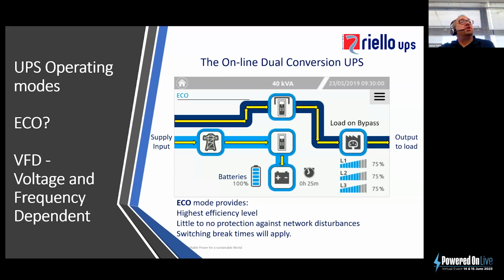Now, one of the benefits of the eco mode of operation is that it obviously provides the very highest levels of efficiency, somewhere near 99+%. However, because the input is effectively connected directly to the output, there is little to no protection against instant network disturbances, and therefore it provides the lowest form of protection for the critical load. So what you gain in efficiency, you lose in the levels of protection.